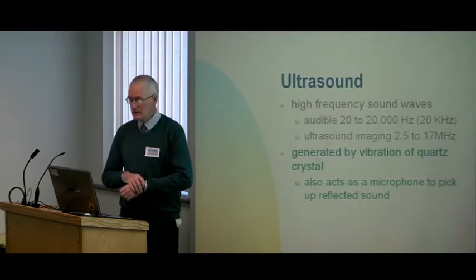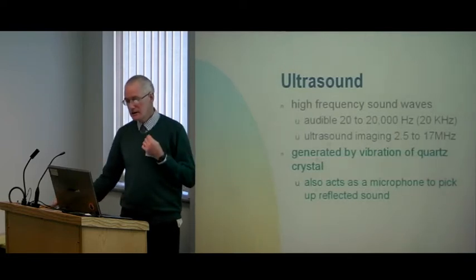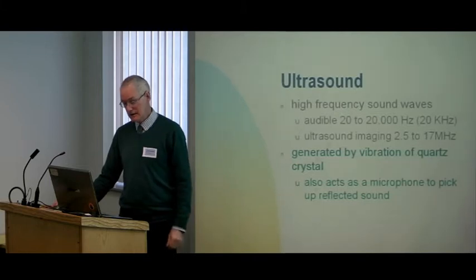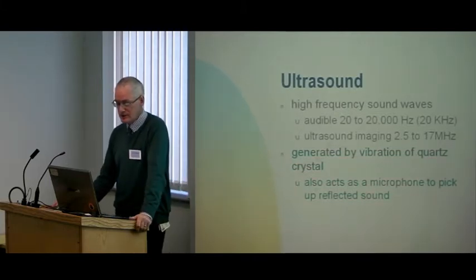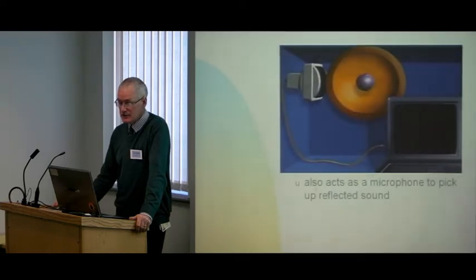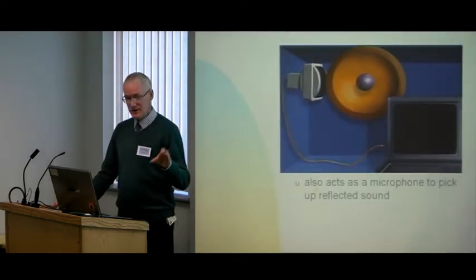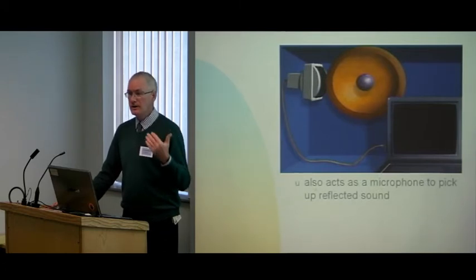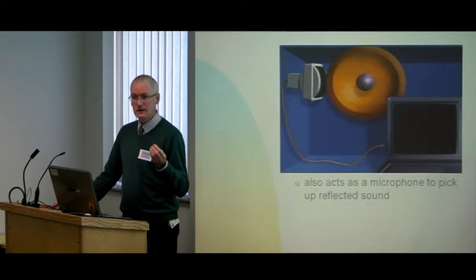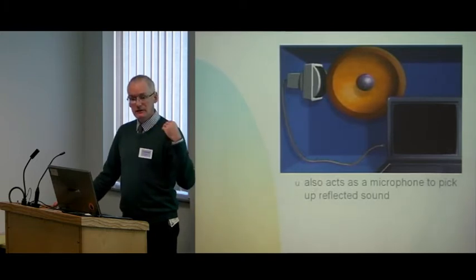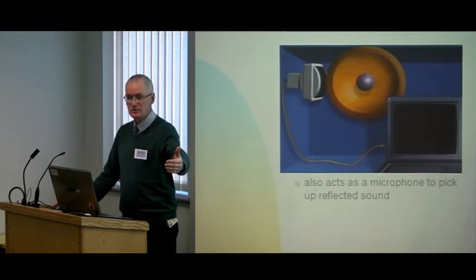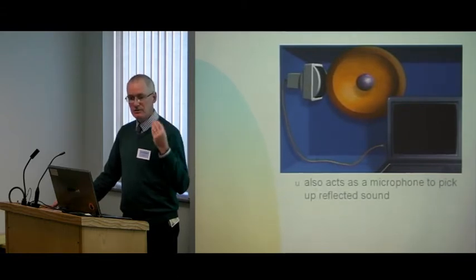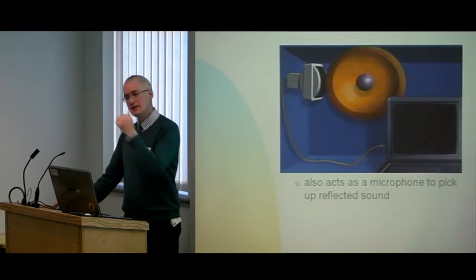It's quartz. So there's a whole array of crystals in the probe, and as an electric current travels through it, that crystal vibrates and produces deformity, which is actually sound generating. So the vibration of a quartz crystal is what produces the sound, and when the electricity is turned off and the probe is left on the patient's skin, it will pick up reflected sound from the body, and that reflected sound deforms the crystal and forms an electric current in the opposite direction. So you've got electricity going into the probe, sound coming out, turn the probe off, sound coming from the patient back to the probe, electricity formed by the crystal.